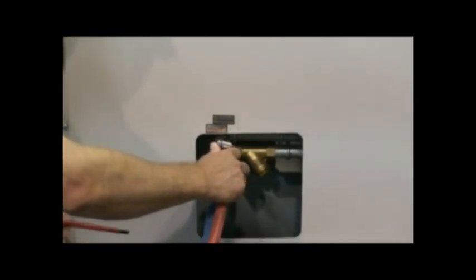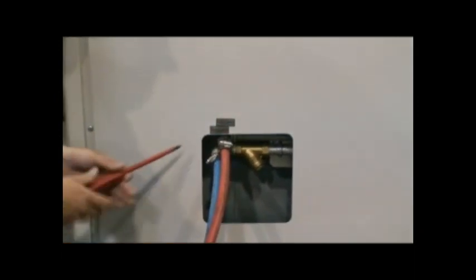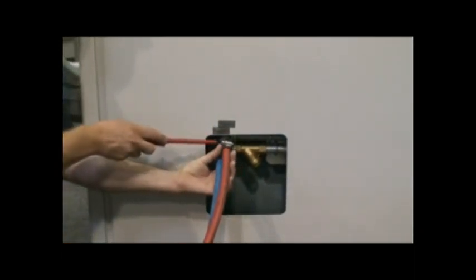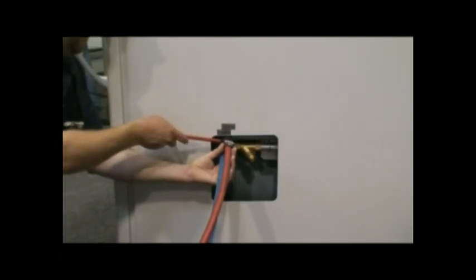On models MJ3-100 or higher, it is ideal to use cooling water supplied to the unit's inline aftercooler for optimum performance. As a routine maintenance checkpoint, make sure all water valves are open and any hose lines are not kinked or leaking.